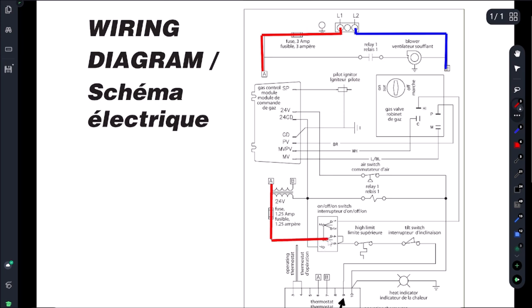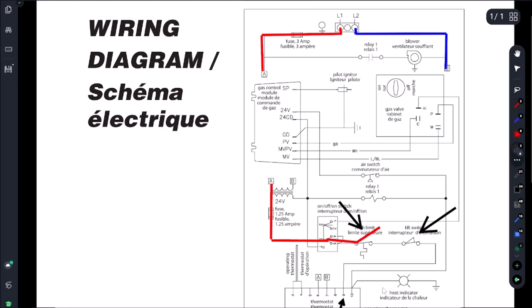So we could be dropping power through this switch, not super likely. I think we're dropping power either through this high limit or through this tilt switch. So let's start by testing this high limit and let's go from there.